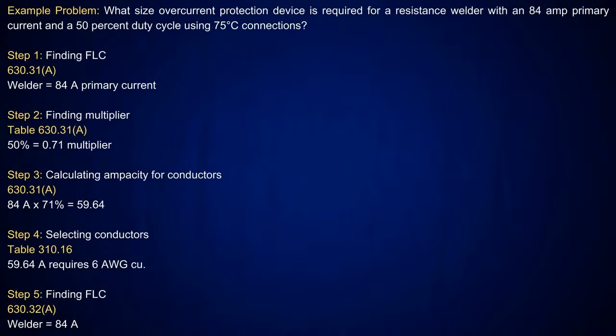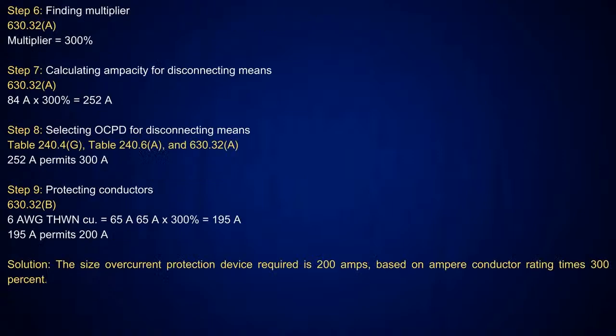All right. Then I'm going to do my overcurrent device. Now, the only difference between these two, when I look at 630.32A and you're doing a resistance welder, is you're going to take it at 300% instead of 200%. Okay? So I'm going to take the 84 amps at 300%, and that's going to give me 252 amps. Now, looking at this overcurrent protection device, I'm going to do it one more time. I'm going to go up to the next standard size just to show you here.